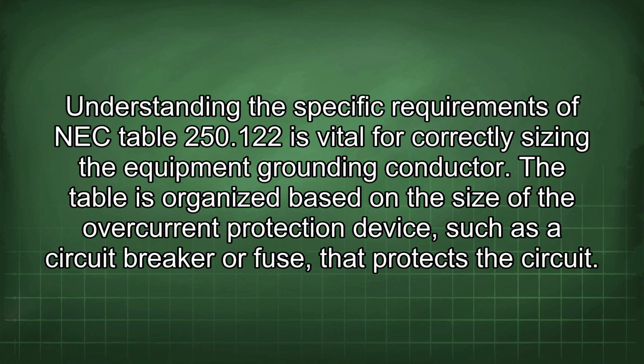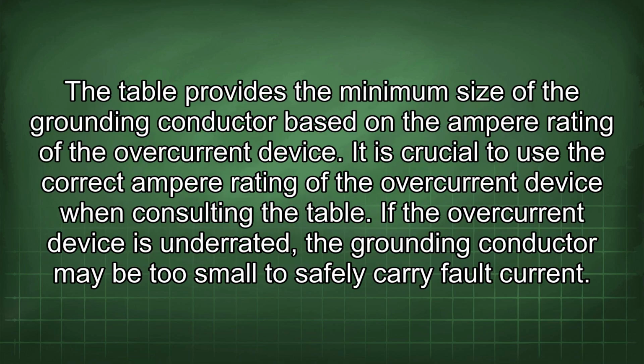Understanding the specific requirements of NEC Table 250.122 is vital for correctly sizing the equipment grounding conductor. The table is organized based on the size of the overcurrent protection device, such as a circuit breaker or fuse, that protects the circuit. The table provides the minimum size of the grounding conductor based on the ampere rating of the overcurrent device. It is crucial to use the correct ampere rating of the overcurrent device when consulting the table.